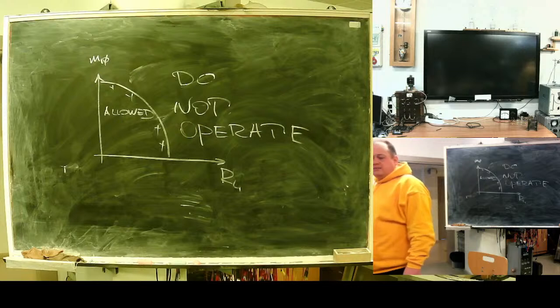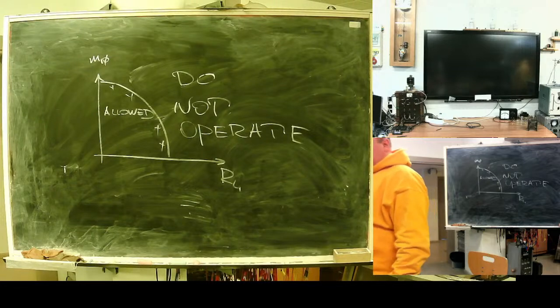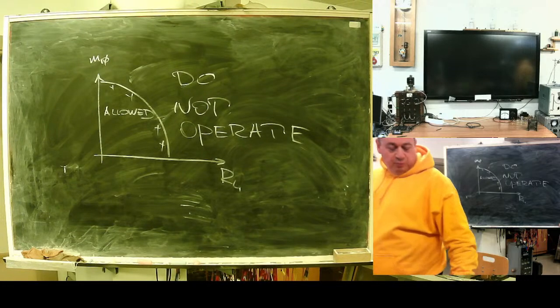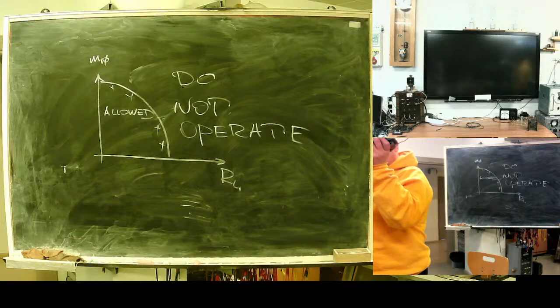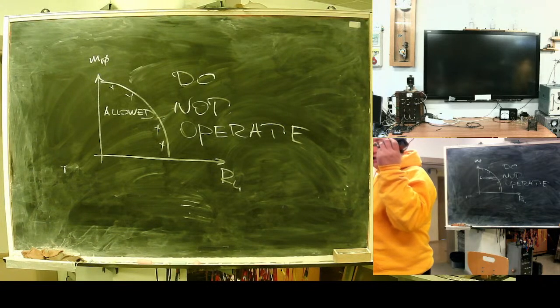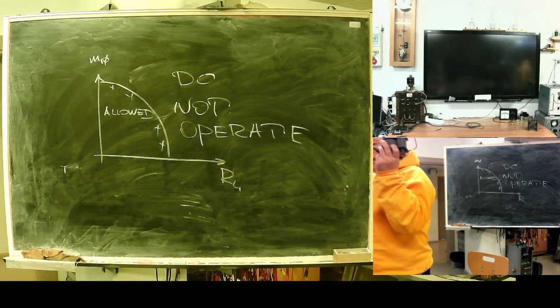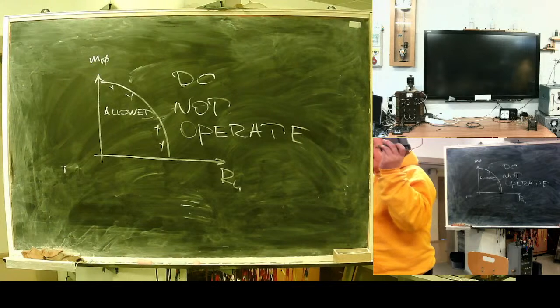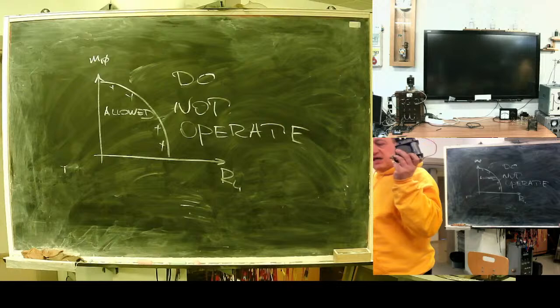Always check the load capability of your transformer, what you're dealing with. If you put a measurement transformer in a protection circuit, it may work, but you should have very small consumption. Higher consumption and you're busted.